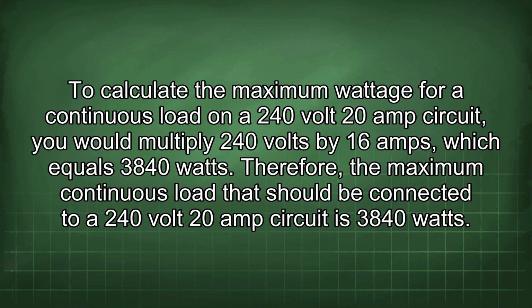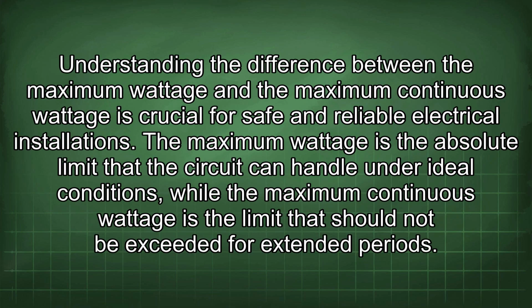To calculate the maximum wattage for a continuous load on a 240-volt 20-amp circuit, you would multiply 240 volts by 16 amps, which equals 3,840 watts. Therefore, the maximum continuous load that should be connected to a 240-volt 20-amp circuit is 3,840 watts. Understanding the difference between the maximum wattage and the maximum continuous wattage is crucial for safe and reliable electrical installations. The maximum wattage is the absolute limit that the circuit can handle under ideal conditions, while the maximum continuous wattage is the limit that should not be exceeded for extended periods.